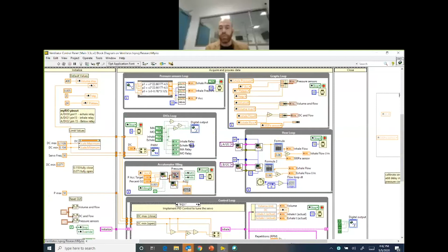We also went a step further. We added a redundant monitoring board that will monitor the number of breaths only, and that will monitor the electrical supply on the machine. This is important. It is outside the main controller, so that it's actually monitoring the main controller to make sure that the main controller doesn't have a problem. If there is a problem with the wiring inside or something like this, we will know automatically.